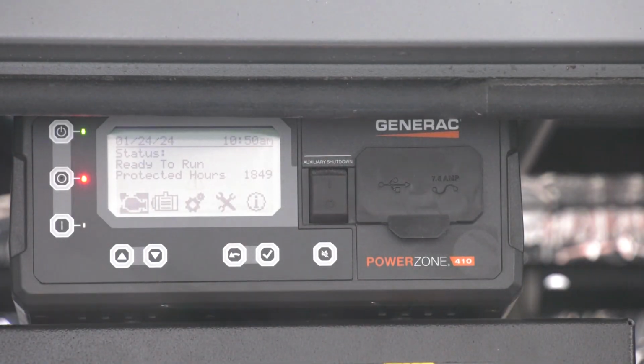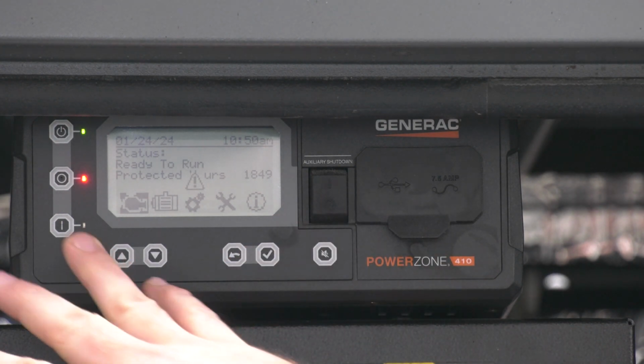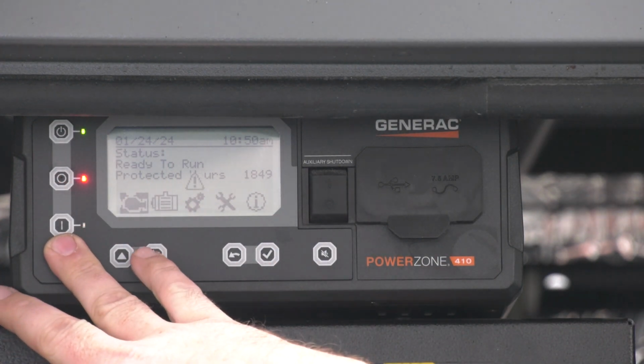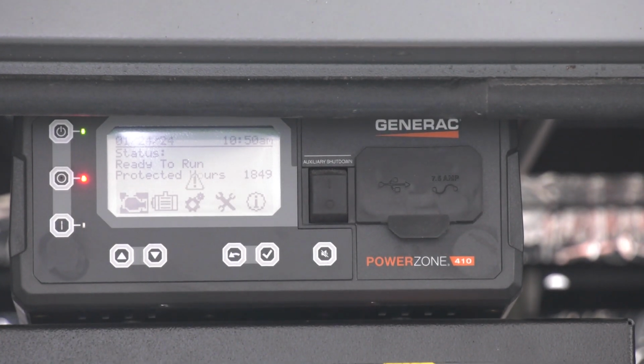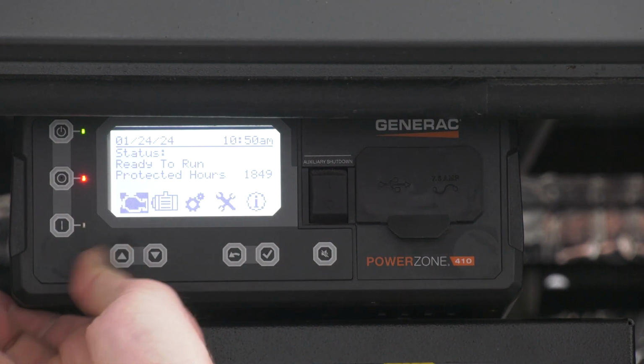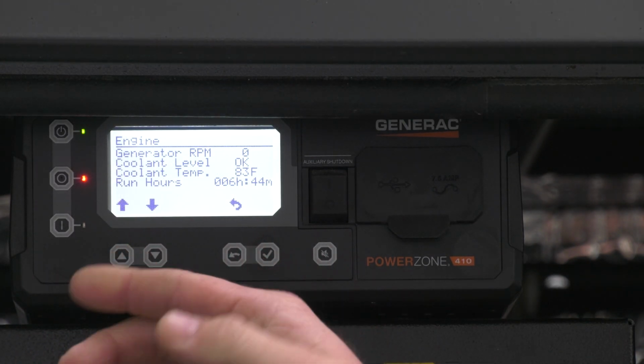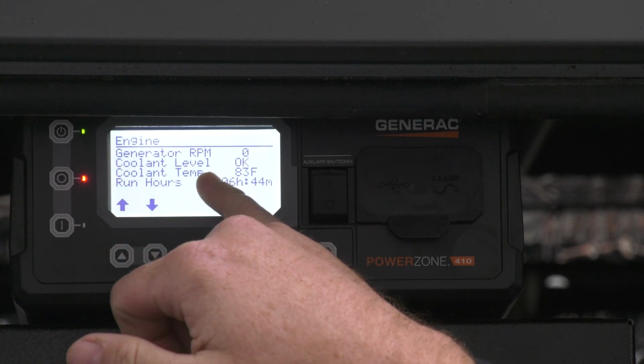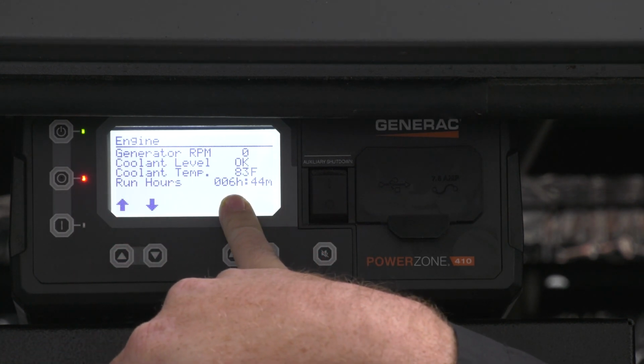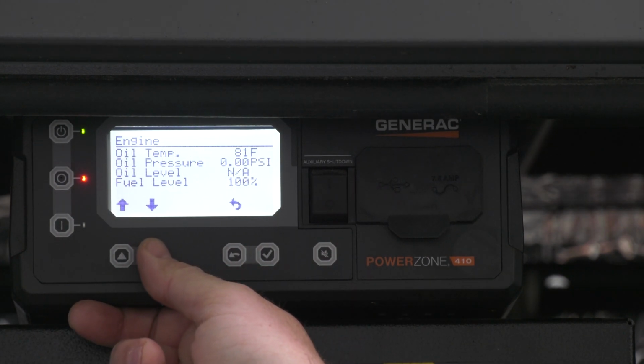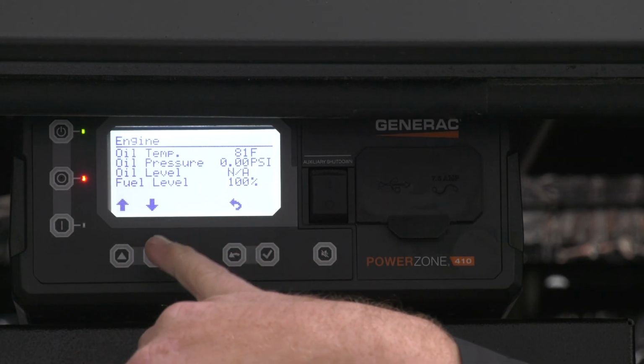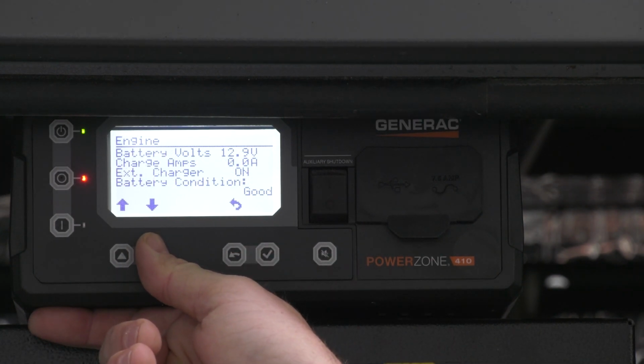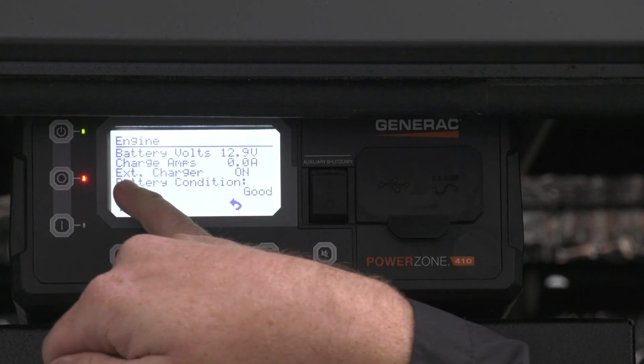Oil fill cap is up here in the top, front valve cover. Start with the basics. This is your on-off switch, key switch. This is an e-stop. You've got an auxiliary shutdown switch here, and you also have on, off, and manual here on this side. If you scroll through your menus, the screen will light up there, hit your check mark. That's your engine information. This will give you RPM, coolant level, coolant temperature, and your run hours. You can scroll down, you'll get fuel level, oil temperature, pressure, all the basic engine information. Battery condition, good. Tells you that your external charger's on.